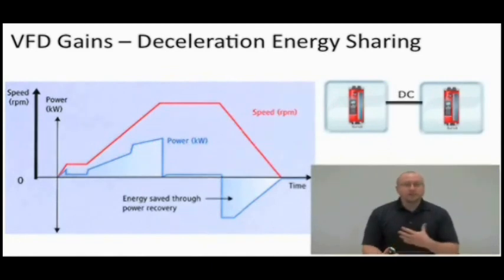Sometimes you can have a brake resistor where it just burns off the energy in the form of heat. Well, that's pretty wasteful. What you could do is maybe have two inverters coupled together. If one is starting when the other is stopping, that's a perfect chance right there to save energy. While the deceleration of one unit, it acts like a generator, pumps energy onto your DC link between the inverters. The other drive can be using the energy to accelerate. That's when you need the most energy, is during acceleration.